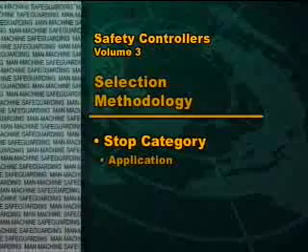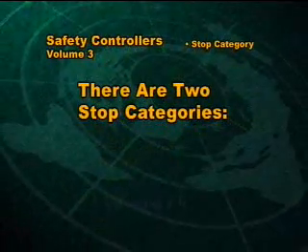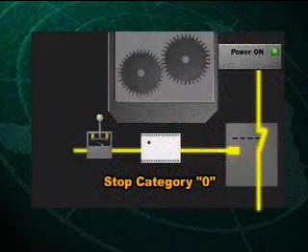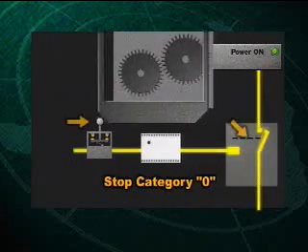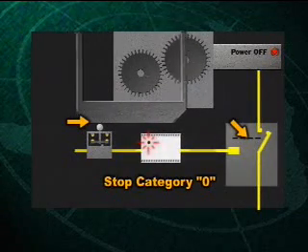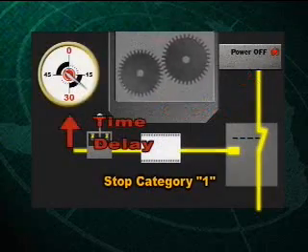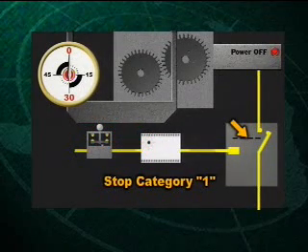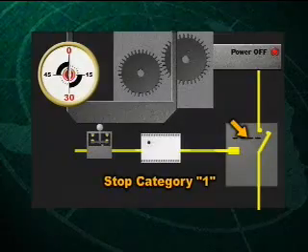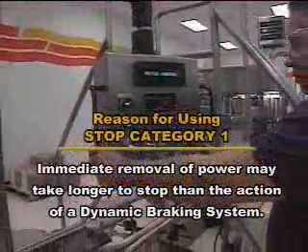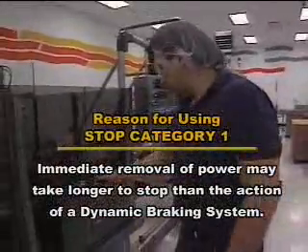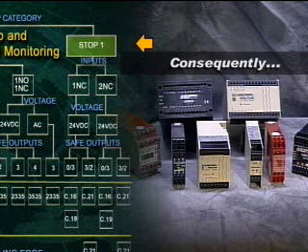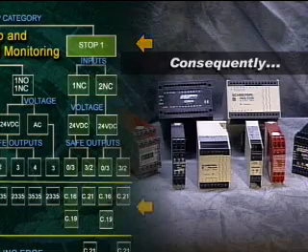Next: stop category desired. There are two machine stop categories, zero and one. Stop category zero is when power is immediately removed from the controlled equipment upon actuation of the safety input device. Stop category one is when, following a stop command, a time delay of up to 30 seconds is allowed before the removal of power. This delay is often desirable in drive systems where the immediate removal of power may result in a longer stop time than could be achieved by the action of a dynamic braking system. Consequently, it is essential the user choose a safety controller compatible with the stop category desired.